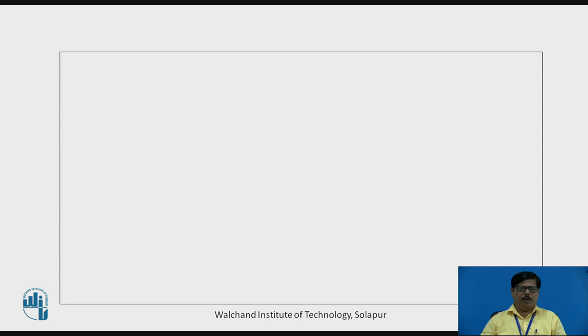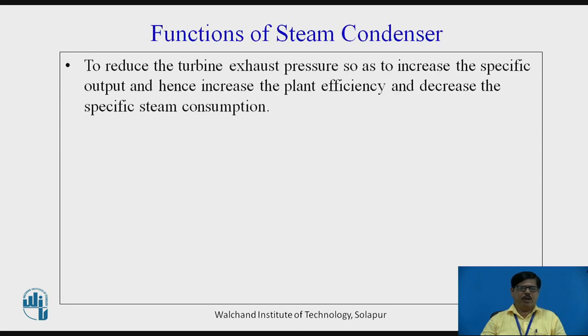The first function of steam condenser is to reduce the turbine exhaust pressure or back pressure of the turbine so as to increase the specific work output. When we expand the steam from high pressure to a pressure less than atmospheric pressure, there is an increase in enthalpy drop. This increase in enthalpy drop gives us more specific work output from the turbine. Since plant efficiency is defined as net work output divided by heat supplied, the net work output will be more, giving us increased plant efficiency.